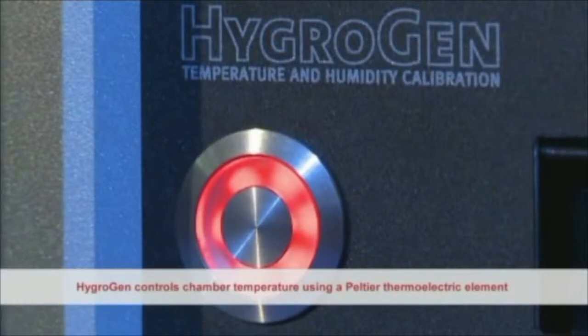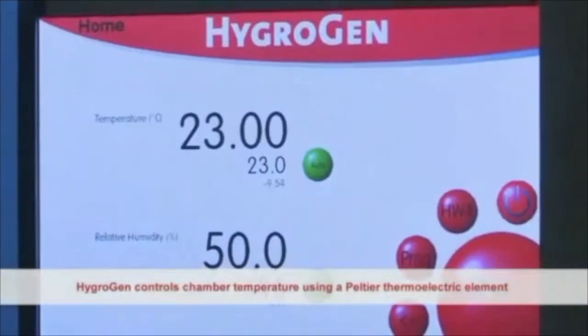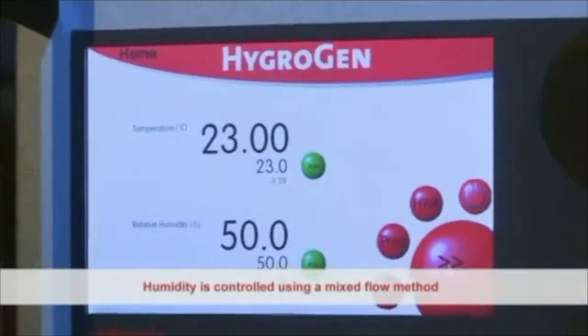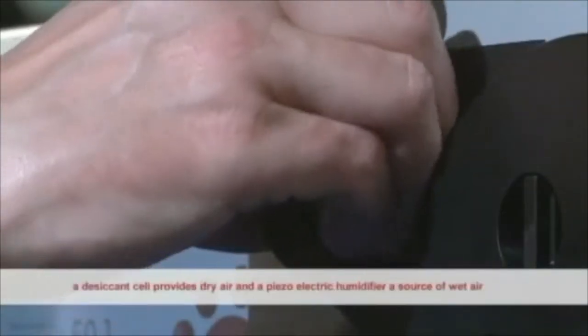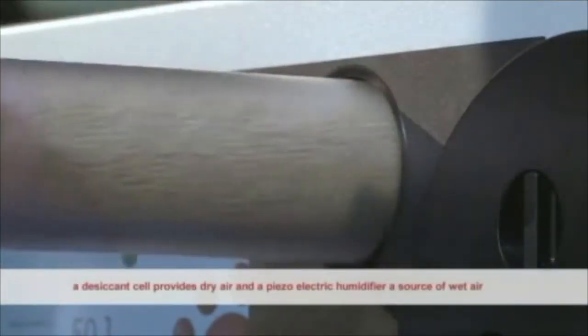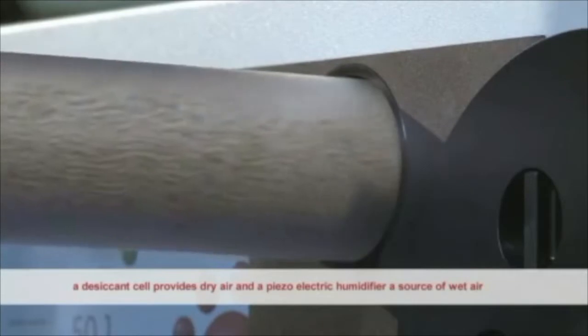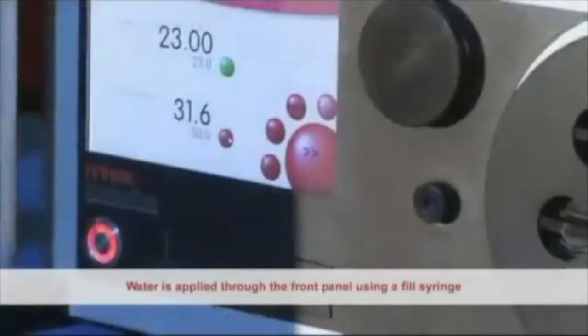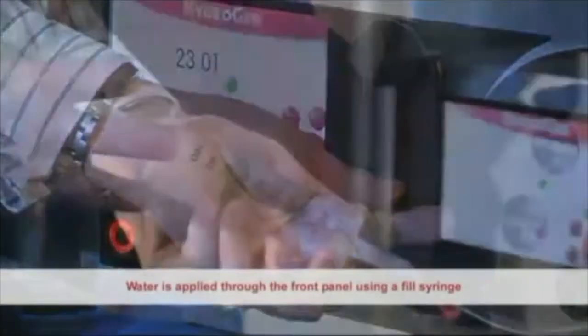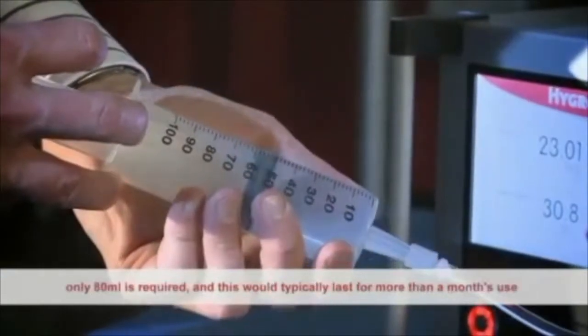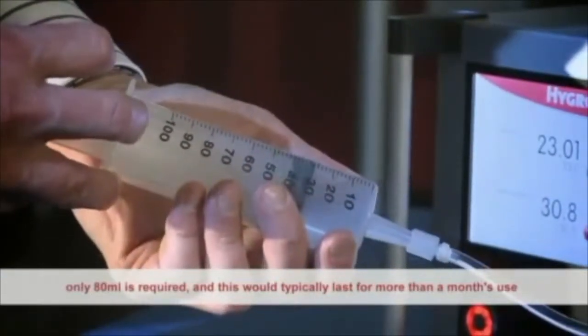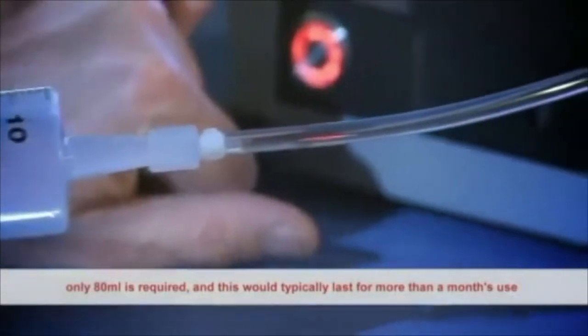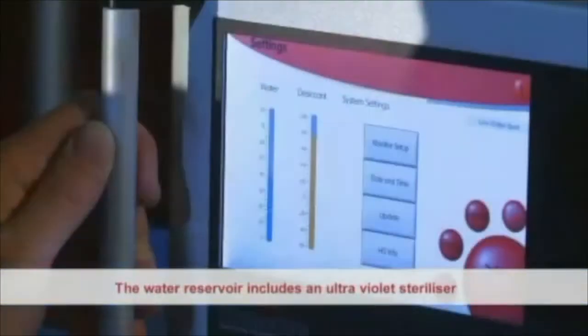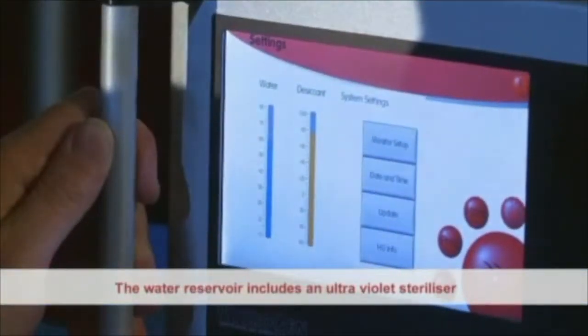HygroGen controls chamber temperature using a Peltier thermoelectric element. Humidity is controlled using a mixed flow method. A desiccant cell provides dry air and a piezoelectric humidifier a source of wet air. Water is applied through the front panel using a fill syringe. Only 80 milliliters is required, and this would typically last for more than 1 month's use. The water reservoir includes an ultraviolet sterilizer to ensure that water quality is maintained.